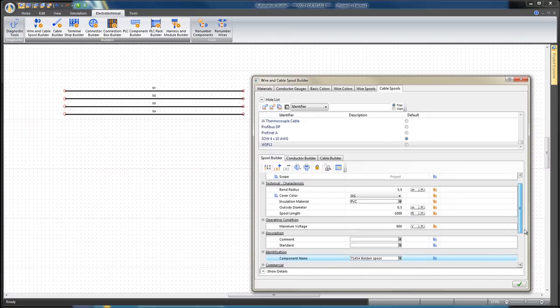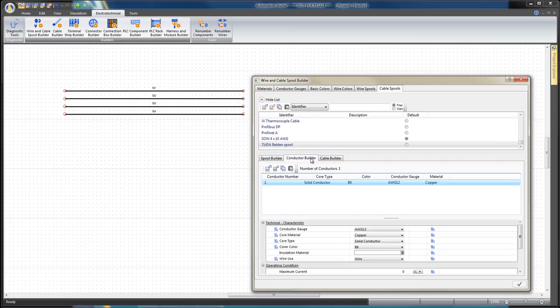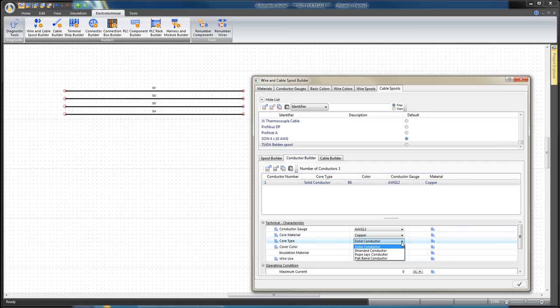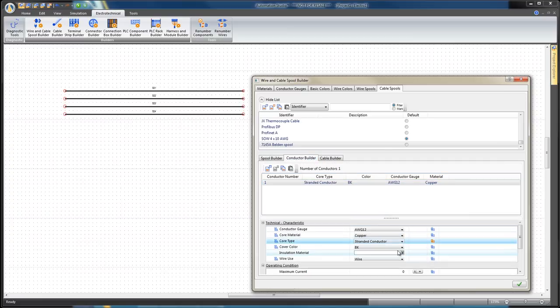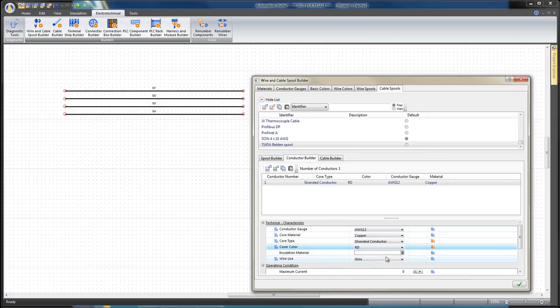Select Conductor Number 1 and set the following values in the Technical Characteristics section. Conductor Gauge, AWG12. Core Material, Copper. Core Type, Stranded Conductor. Cover Color, RD for Red. Insulation Material, PVC. Wire Use, Wire.